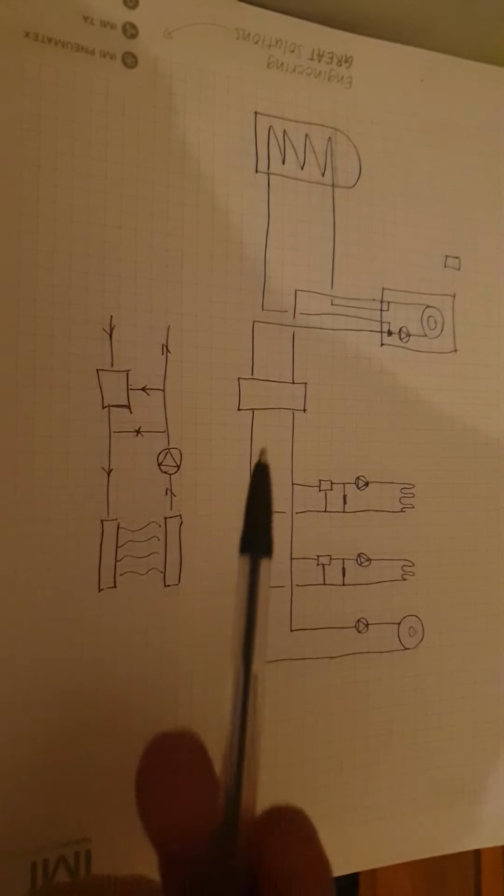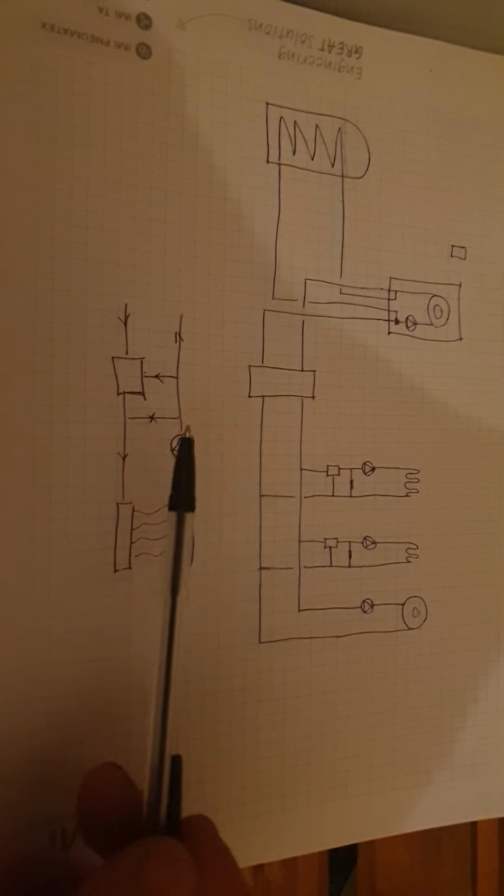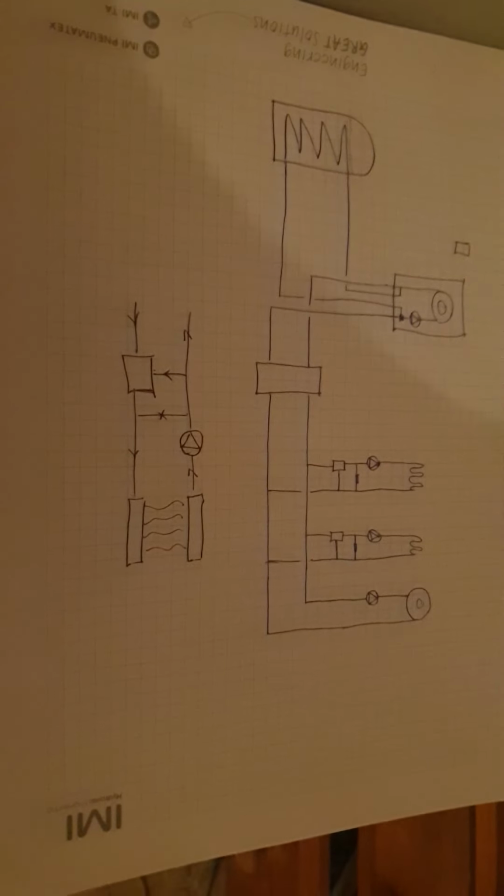What you really want to do is to put in your close coupled T's or your low loss header, and then supply off your underfloor heating system after that. So the underfloor heating system can take whatever flow rate it requires, and your radiators get the flow rate they require. And what people have been doing is putting in close coupled T's.